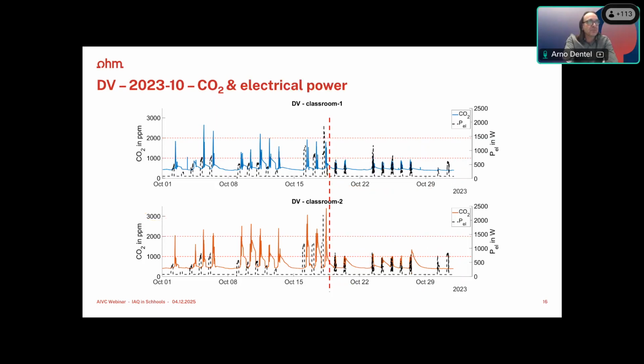We correlated the electrical demand of the air handling unit. And we saw that the air handling unit is not running at occupied times. It is running in the night. It was the wrong time schedule installed at the air handling unit. So it's a fault here. And in mid October, you see the CO2 concentration measured and the electrical demand of the ventilation system at the same time. So we adapted the time schedule for this.